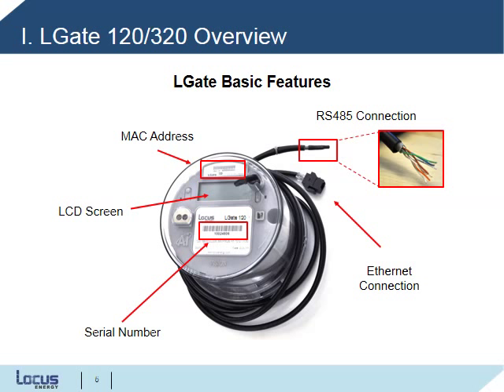These meters are pre-programmed with our latest firmware version. If the LGate requires a firmware or device configuration update post-installation, we can send these updates over the air without having to have someone log in to manually program new settings. These LGates will check for new updates on a regular schedule, which means that we can post an update for the LGate without having to ping it over the AT&T network or the local area network. The LGate will automatically download the update when it checks in on schedule.